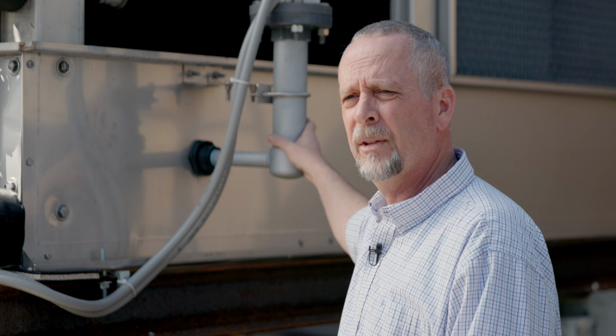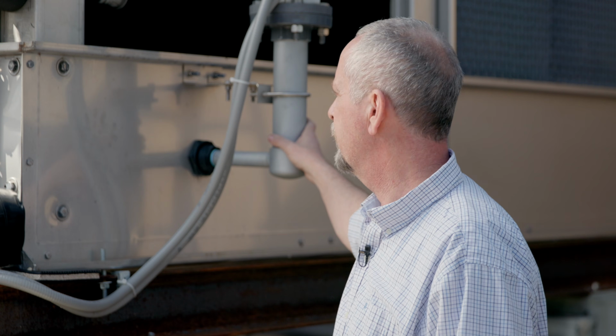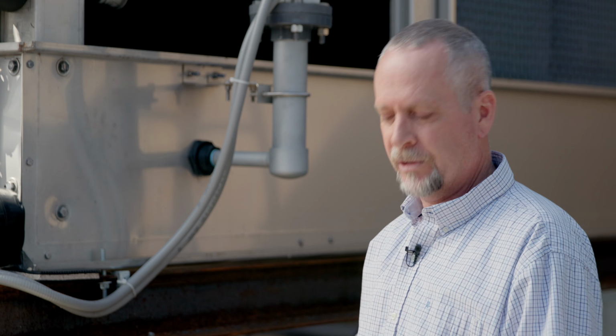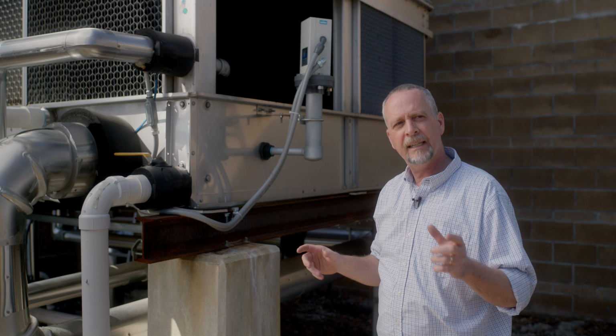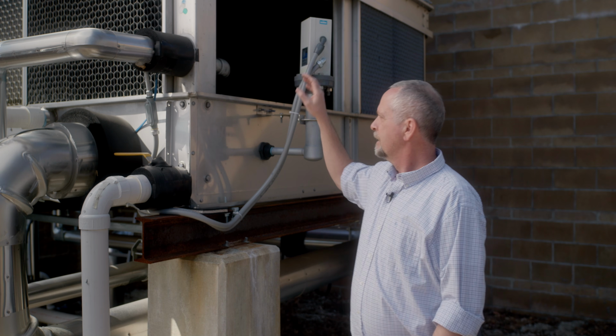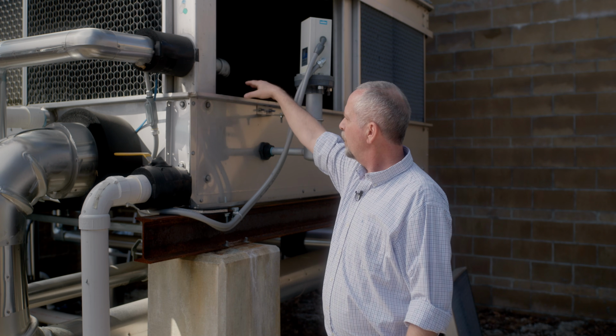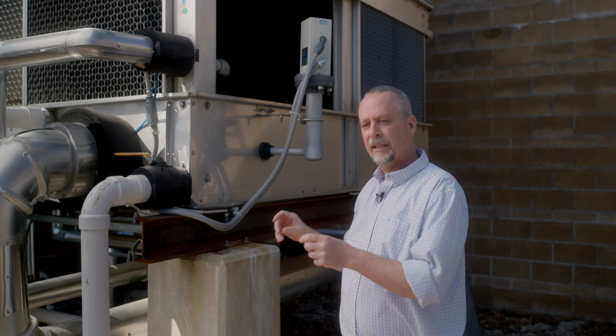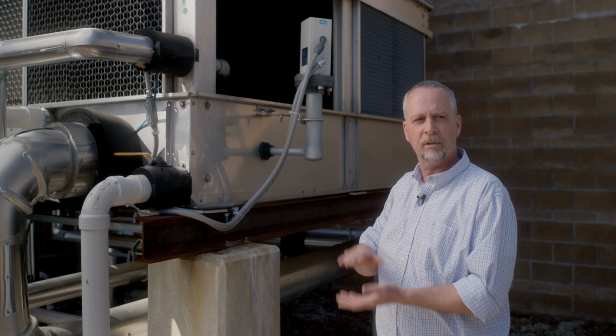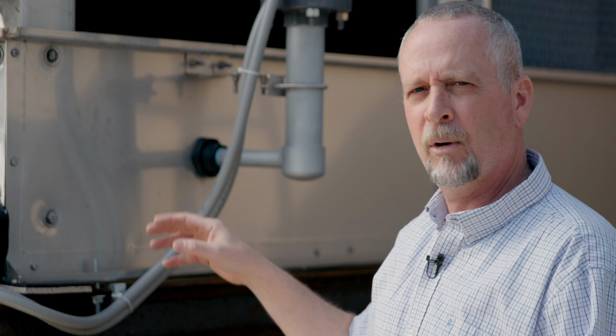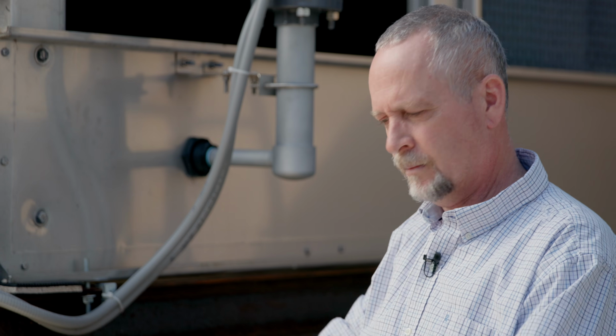There's one other way to fill this tower called a mechanical float valve. Very similar to what you'd see when you pull the top off your toilet tank and you got that ball float in there. That's exactly what we're doing here. We got a ball float that's adjustable on a rod, and you manually set where you want your water level to be, and then the tower fills. When that float drops, the valve opens, we fill the tower. As the float raises with the water level, gets to the desired level that you've manually set, it shuts off the water flow.